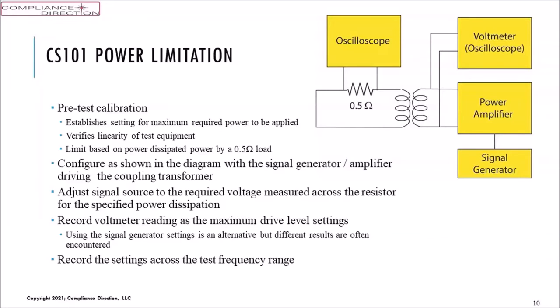We measure the power amplifier output with a voltmeter. Having the measurement with the voltmeter at that point allows us to adjust the amplifier gain and have the voltage proper. If I measure at the signal generator output, I'm not allowed to vary the gain of the amplifier without a recal. So if I come to higher frequencies where I might need to raise the gain of the amplifier to get a signal out of noise, then we need to compensate for having that measurement. So I typically use the voltmeter located at that point.